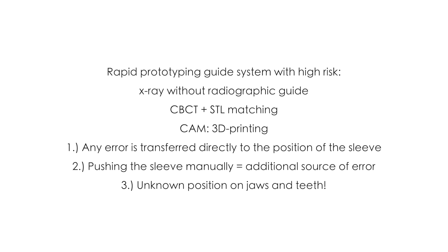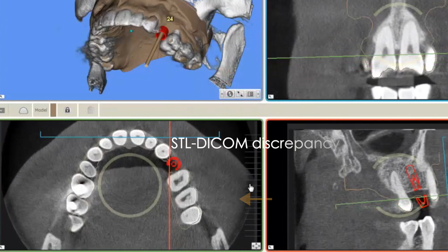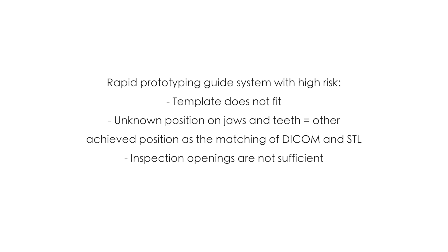This error then continues throughout the whole system and might not be recognized by the CBCT. Due to this, the template has a geometrical error. It may not fit correctly or have a different fit than previously designed by the matching of the data. And that is why this system has such large deviations in implant drillings.